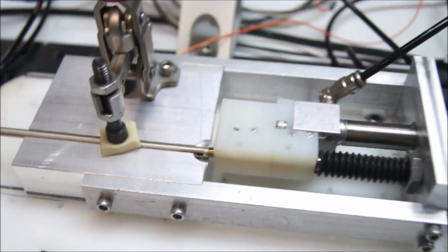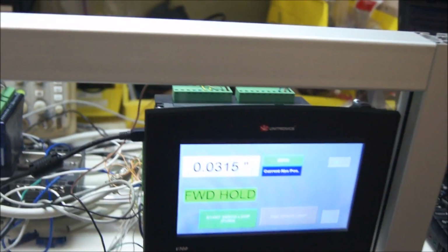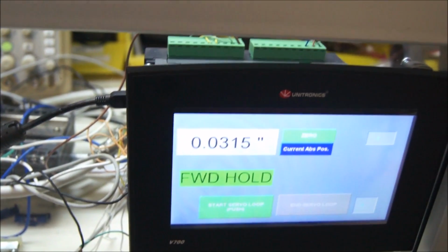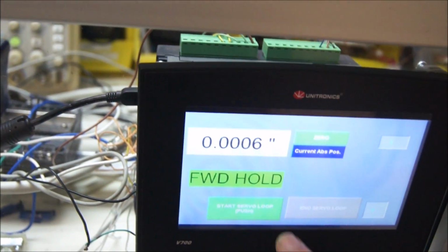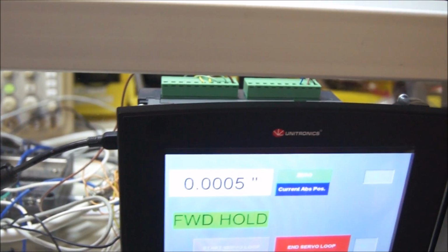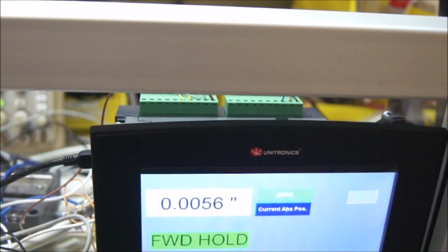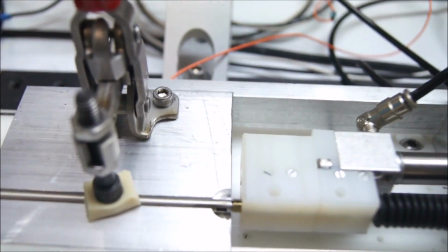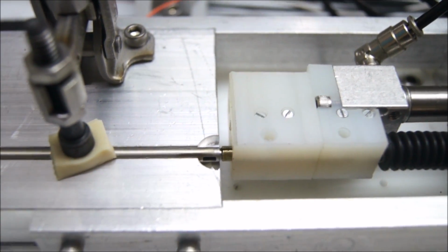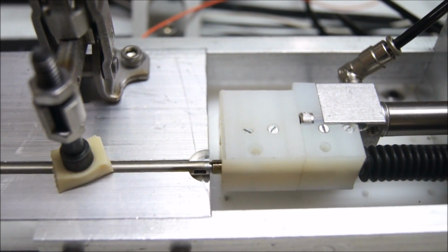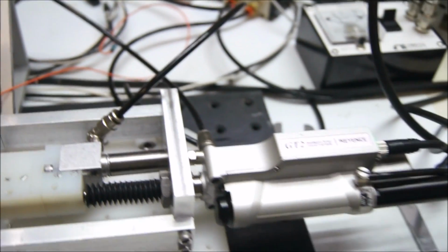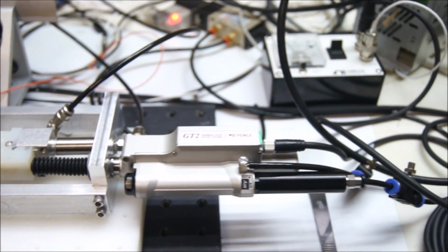And we're going to get ready to do the first step, which is to move the pusher to 0.210. Right. So now we begin to move the pusher forward, looking for the 210 position. So we 0, and then we start. So right now it's picking up the backlash from the first position. Now it's beginning to move. Okay. You can see the pusher is moving the probe out. The scale's picking up the measurement.